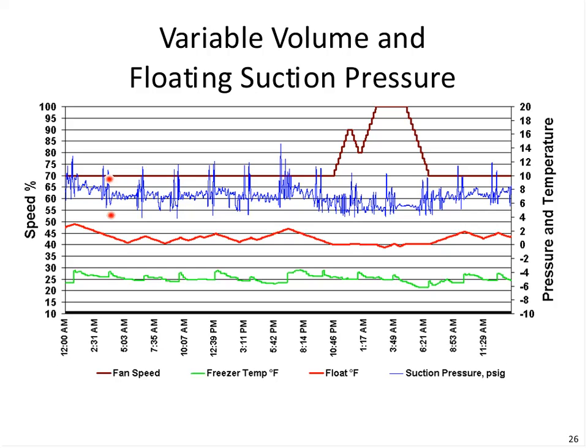Now, as the day is progressing through here, we can see the float in temperature was really, well, here's 0 degrees, so we're floating the temperature up a little bit as the temperature is lower in the space. Then we go up with the float. The temperature goes a little bit above the set point, so reduce the float. So our float is going up and down, and notice it's about a couple of degrees throughout the day.